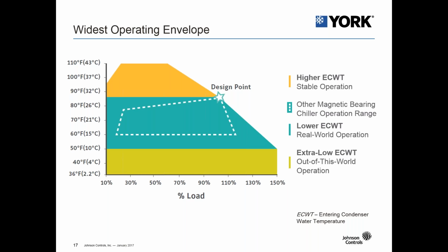And what we'd like to highlight is the capabilities of the YMC squared, the York YMC squared. So the York YMC squared is able to take higher entering condenser water temperatures. We're able to overspeed the impeller with the magnetic bearings to overcome that system pressure differential, the buildup in the condenser, to avoid surge and stall that may be experienced on other chiller packages.